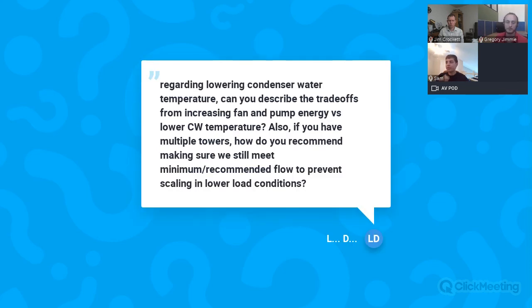Okay. So we have a question. Regarding lower condenser water temperature, can you describe the trade-offs from increasing fan and pump energy versus lower CW temperature? Also, if you have multiple towers, how do you recommend making sure we still meet minimum/recommended flow to prevent scaling in lower load conditions? Either one of you feel free to jump in here.